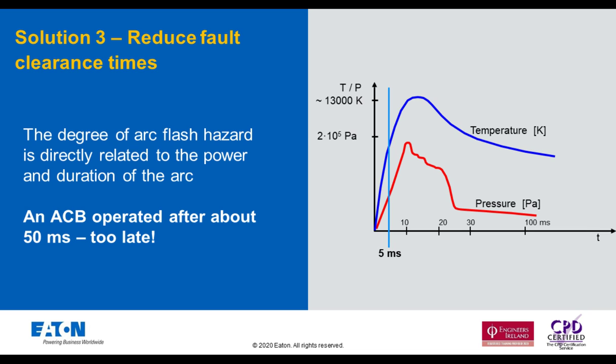So what's the next solution? The next solution really is to reduce the fault clearance times. Typically, if you rely on the air circuit breaker, which is generally an incoming device to a switchboard, it will operate in probably up to 50 milliseconds. And during that 50 milliseconds, you've got lots of effects by the arc.